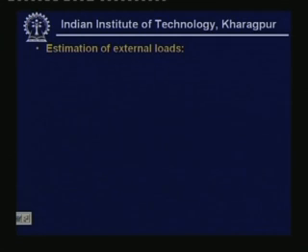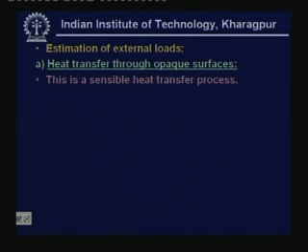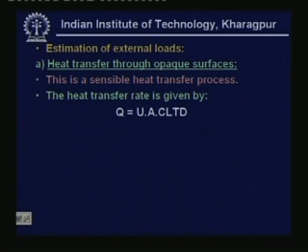Now let us look at estimation of external loads. First, heat transfer through opaque surfaces — all walls, roof, floor, doors, etc. The heat transfer rate through these opaque surfaces is sensible heat transfer only. It is given by Q = U × A × CLTD, where U is the overall heat transfer coefficient, A is the area, and CLTD is the cooling load temperature difference. For sunlit walls and roof, CLTD has to be obtained from CLTD tables, as discussed in the last lecture.